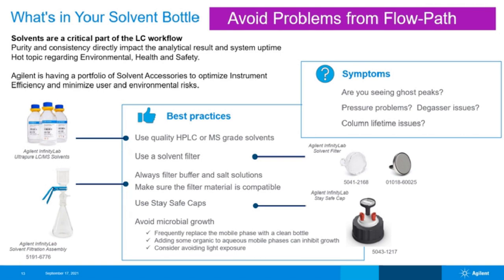Aqueous mobile phase is a perfect host for microbial growth, especially sitting in a warm lab or in sunlight. Microbes are tiny and can accumulate in the smallest corner of your system or even pass through the column inlet frit and into your column, causing system contamination and high back pressure. Don't let aqueous mobile phase sit for many days. It should be replaced frequently. You can always add a small percent of organic solvent to your mobile phase, like 5%, to inhibit microbial growth. There are also amber bottles that can help reduce light exposure to your solvent.